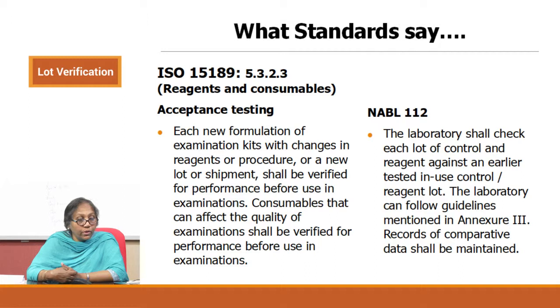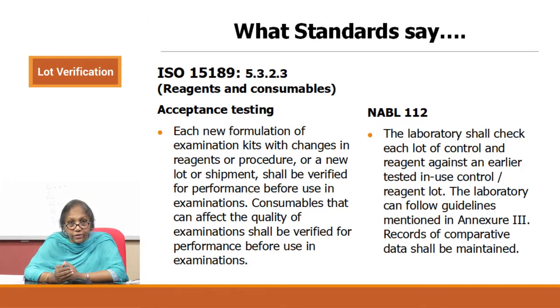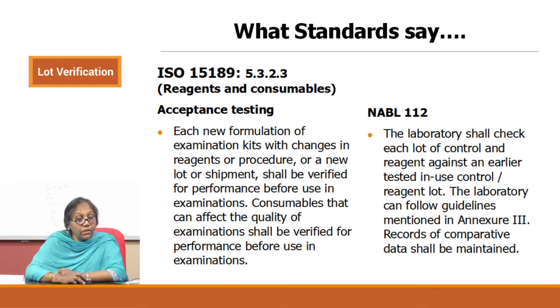The laboratory can follow guidelines mentioned in Annexure III, and records of comparative data shall be maintained. This is an important activity. In the case of controls, we already talked about parallel testing — that is your lot verification — running it parallel to the existing lot of QC. But in the case of reagents and calibrators also, you have to find a mechanism to verify what you are reporting will be correct, and documentation of all comparative data should be recorded and maintained.